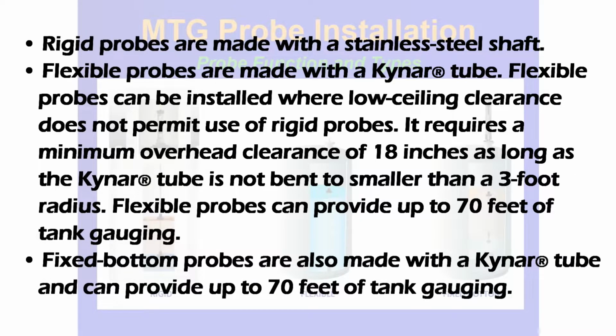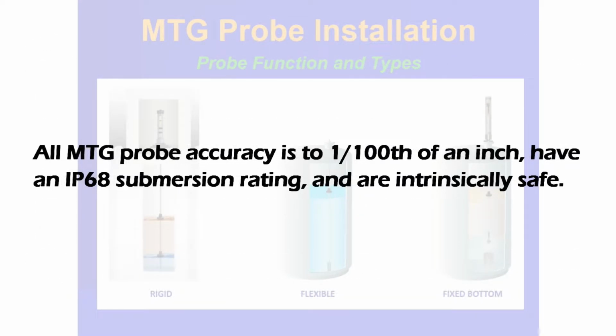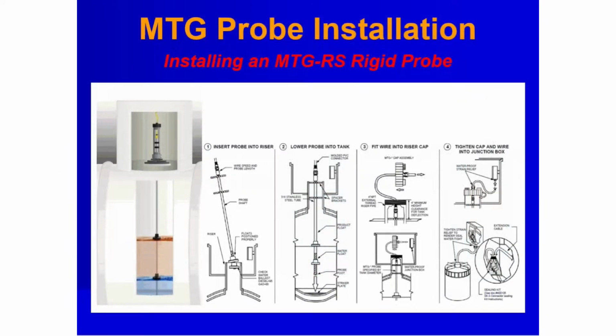Fixed bottom probes are also made with a Kynar tube and can provide up to 70 feet of tank gauging. All MTG probe accuracy is to 1/100th of an inch, have an IP68 submersion rating, and are intrinsically safe. Please note, rigid probes may touch the bottom of the tank. The steps for installing an MTG-RS, rigid stainless steel, are as follows.